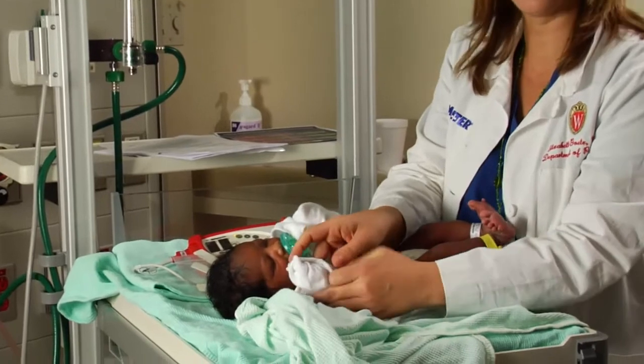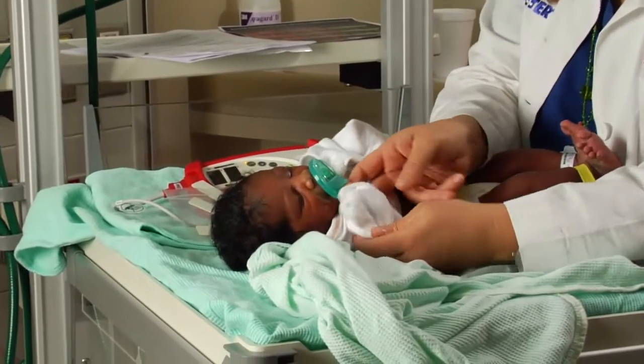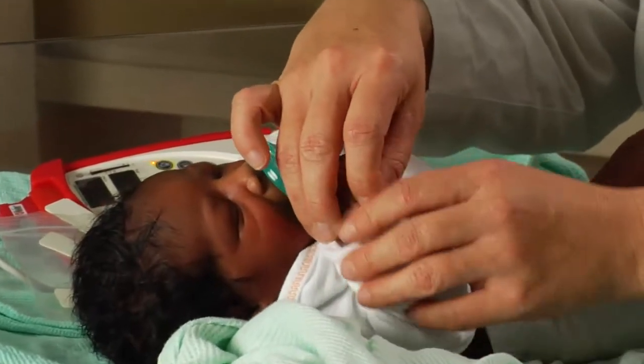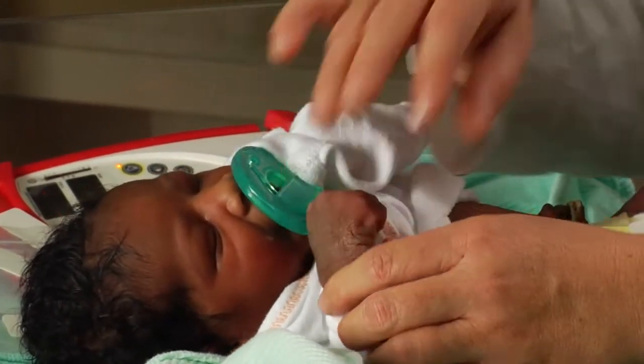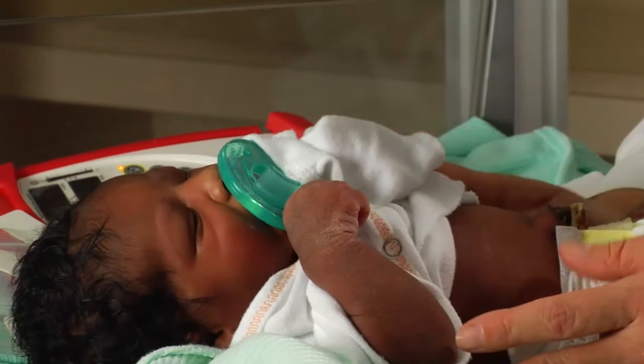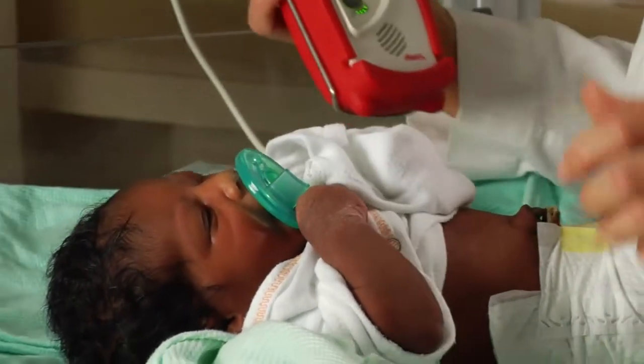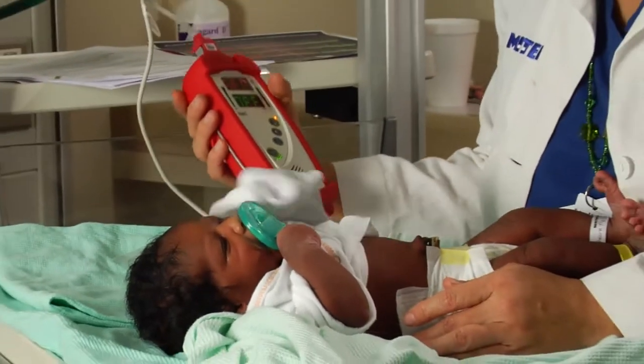usually in the right hand. We have to get the screen on the right hand and one foot. It's possible to do them at the same time, but it's much easier to do them in sequence. Doing it at the same time may require you to have two sets of equipment.